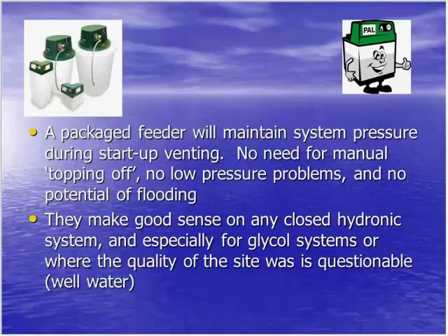So, our package system feeders are sized such that there's enough volume of fluid in the feeder to get you through the first few weeks of operation to vent that 3 to 5% of the total system volume that will be vented out, all that oxygen or air that's going to be vented out of your system. There's going to be adequate fluid in that tank to keep the boilers running and things operating correctly. So they make good sense in any closed hydronic system, and especially for systems with glycol solutions in them or where the quality of water on site is questionable. Also, if you have well water and don't want to risk contaminating it through a failed backflow preventer, I know I wouldn't want to risk that, so it's a good reason to use one there.